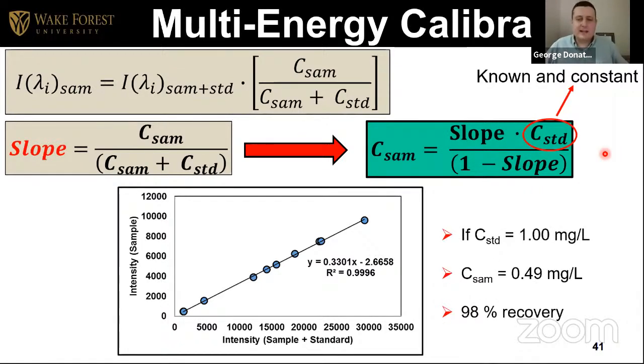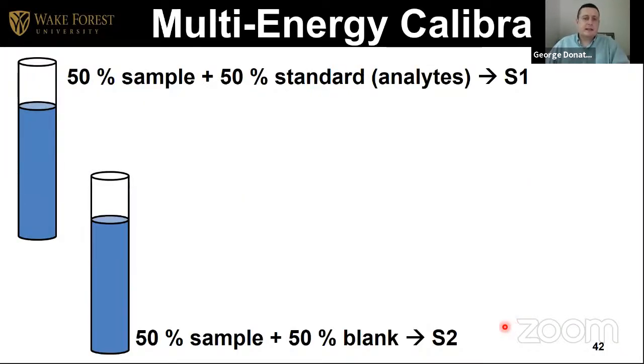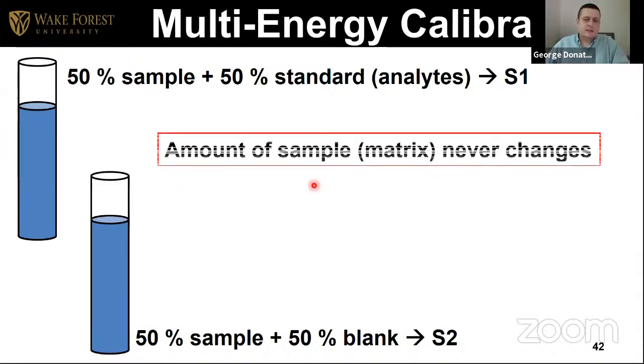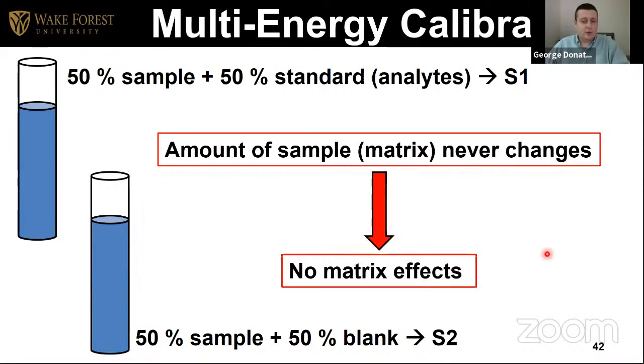So in this example, just to put some numbers on it, let's say the concentration of the standard is 1 ppm. When you apply that slope to this equation and 1 ppm, you get 0.49 milligrams per liter. In this example, it was expected 0.5 milligrams per liter, so 98% recovery. Again, the way the setup works, there is the same amount of sample in both solutions in every change, so no matrix effects expected, just like SDA.